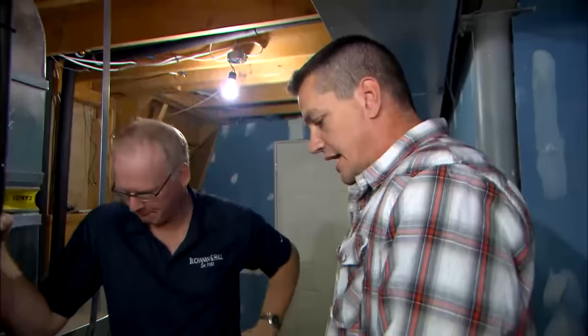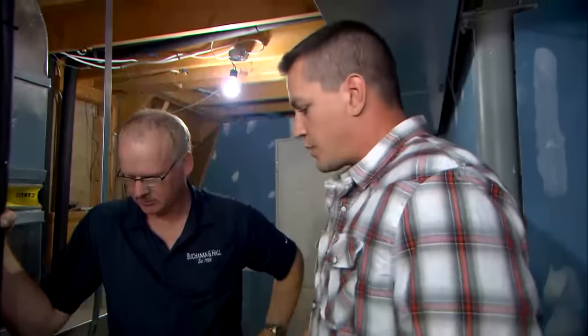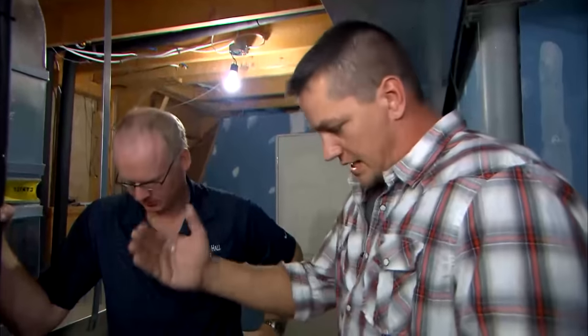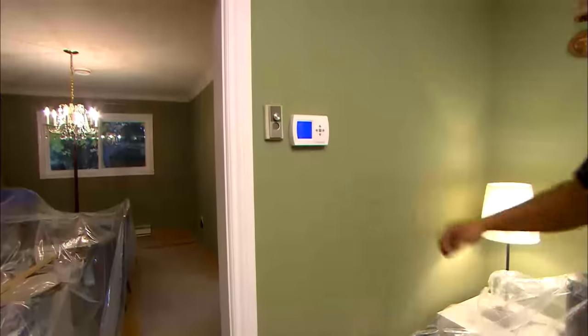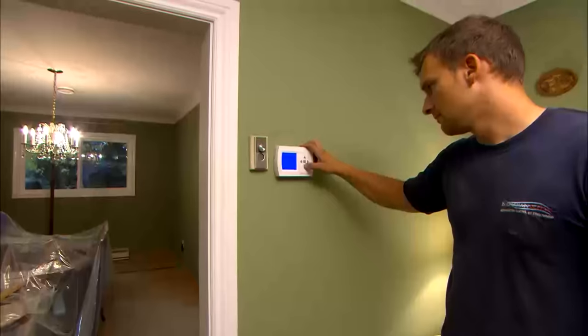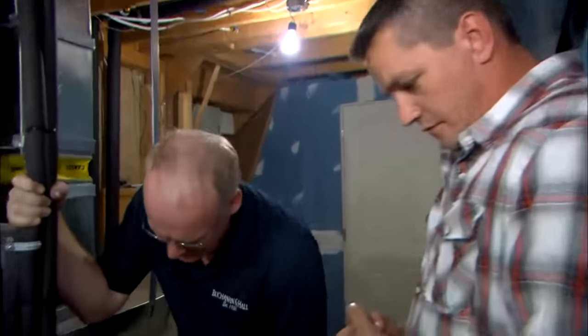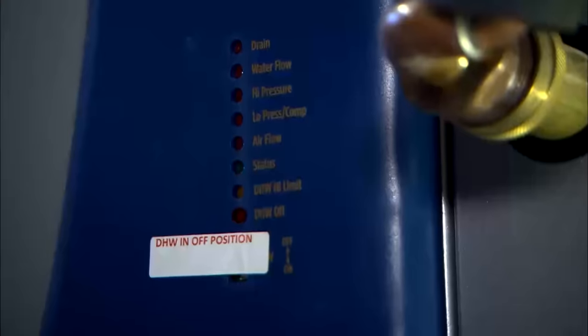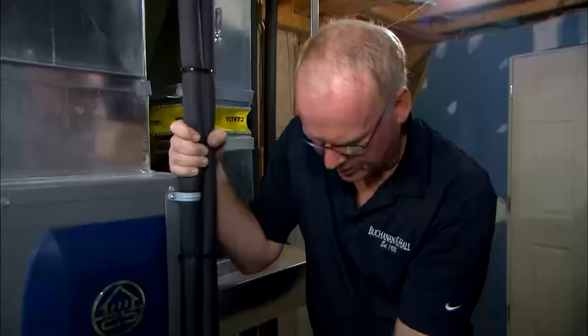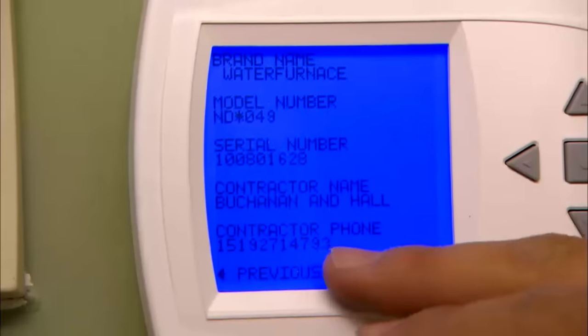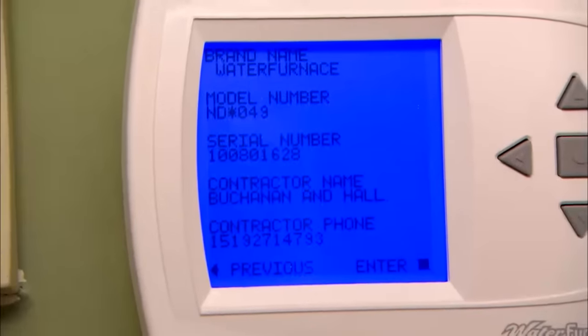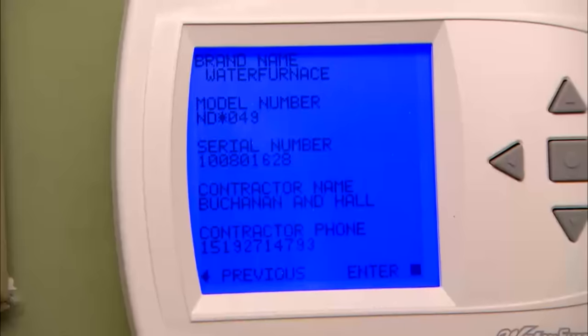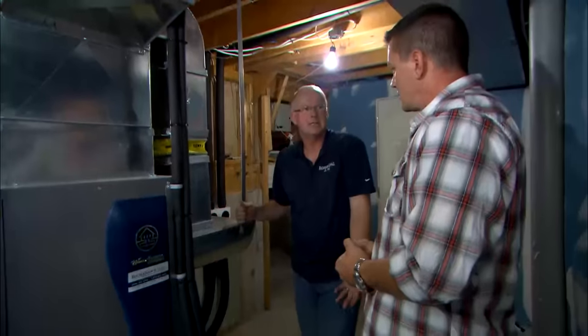One of the other complaints they had was they didn't know who to contact. When they needed to fix it, there was nothing here, the paperwork had been lost over the years. They had nothing. What you're telling me is this system will actually tell them what's wrong. Your number's on the inside of the thermostat upstairs, and it'll read it out to them so they can call and know exactly what's wrong with the unit. There are diagnostic lights right on the front of the machine, and if there's a fault, it'll read here, but it'll also show what that fault is on the thermostat and store that there. It even displays the type of machine, the model, the serial number — all that information is right there handy for them. If it's done properly, they're a great system.